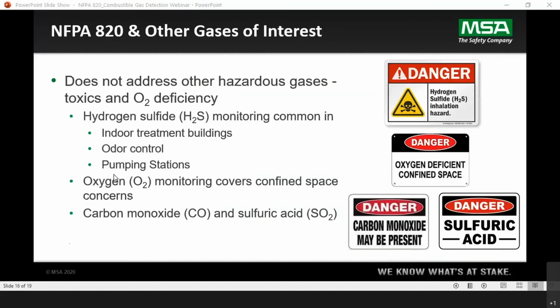Oxygen is a concern especially in smaller spaces, because they are considered confined spaces, like lift stations and pumping stations. So oxygen is also added. Carbon monoxide is common as well if you have internal combustion engine trucks that deliver inside a building to, say, storage areas. Acid treatment will also have other gases that we'll monitor for wastewater, but not necessarily recommended by NFPA 820.